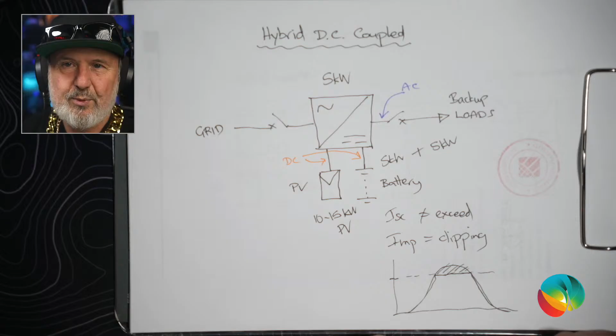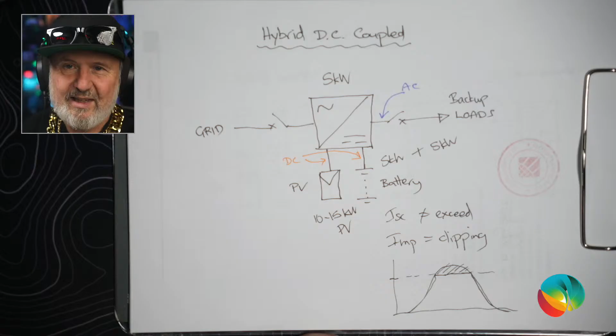In fact, there's one more requirement in 5033: we put in a 25% safety margin on top of that. That means your module's ISC times 1.25, that's the safety margin, must be less than the ISC of the solar input of the hybrid inverter or solar inverter.